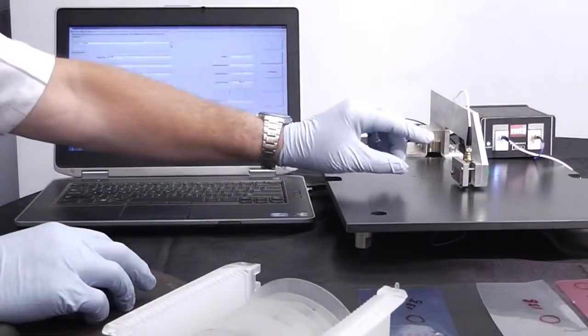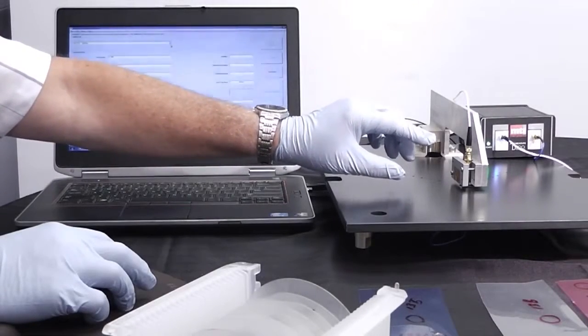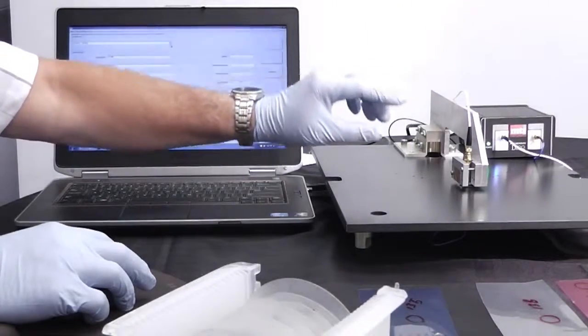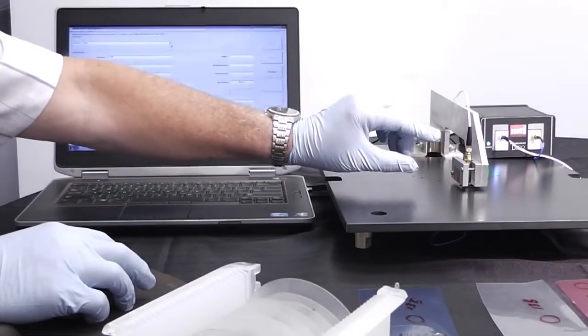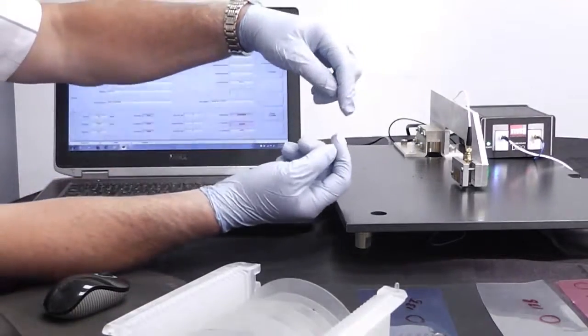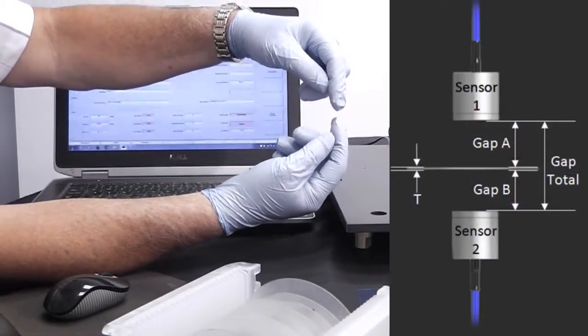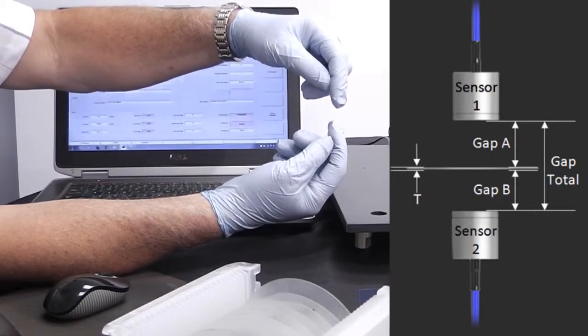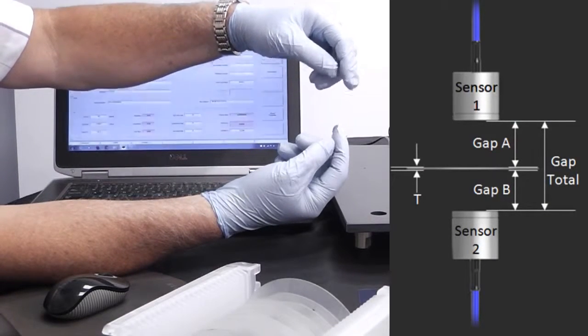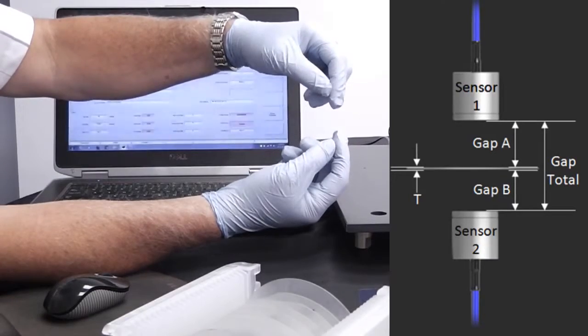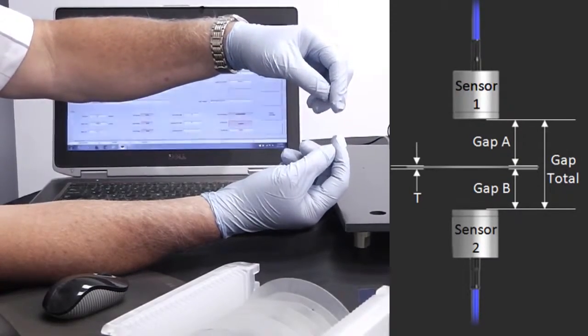target. For measuring the thickness of dielectric materials or non-conductive materials, the first thing we have to do is set the probe gaps. So what we want to do is to have our 2 probes a specified distance apart, and that distance is going to be 2 times the range. The probes each have the same range, plus the thickness of the target, and then you're going to come in a little bit closer.